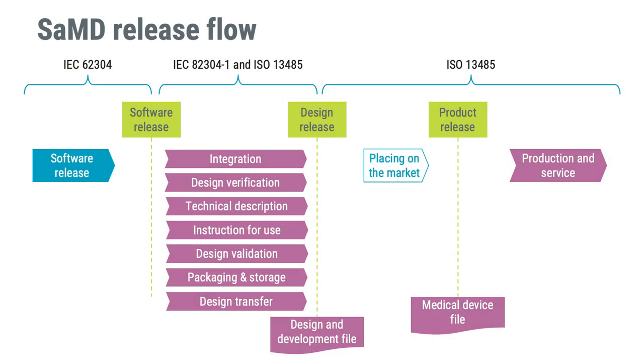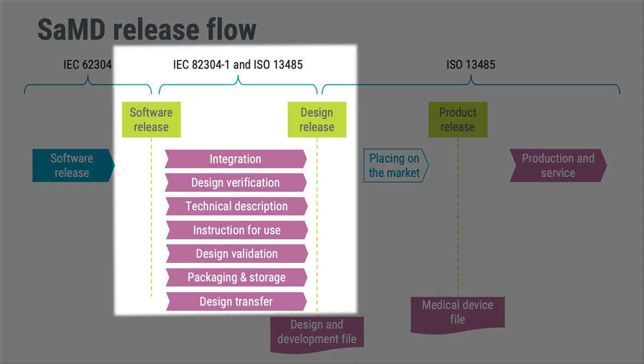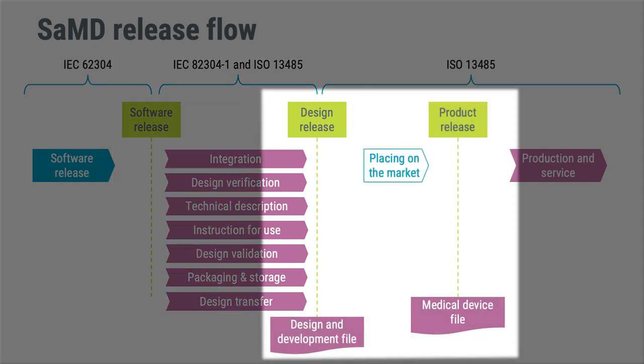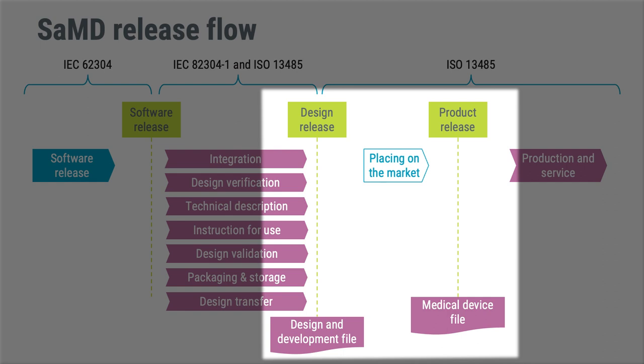Product documentation is usually overlooked in a software release. A complete medical device release flow spans many more activities than the software release. There are requirements for design validation and accompanying documents such as the instruction for use. These activities will result in what I call a design release. Once the design release is done, you may need to wait for regulatory approval before product release and placing the product on the market. After the initial product release, you can usually manage non-significant changes without new third-party regulatory approval.